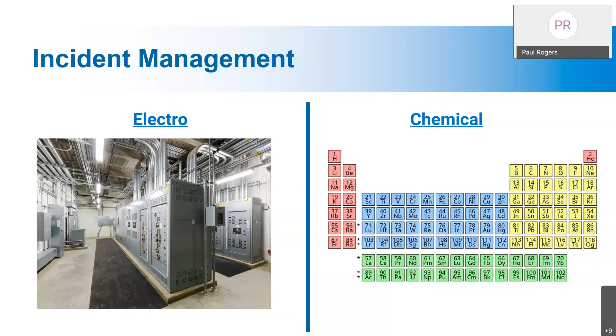We also know that when we shut down any electrical emergency, we'll shut off power, and we will not operate until we know the power is off. But when you're dealing with batteries, shutting these things down does not release the energy. That became a major concern operationally for firefighters, because the energy gets isolated in the enclosure, in the battery, or in the system itself, and it doesn't go anywhere. It stays isolated there. That's what we mentioned before about stranded energy.